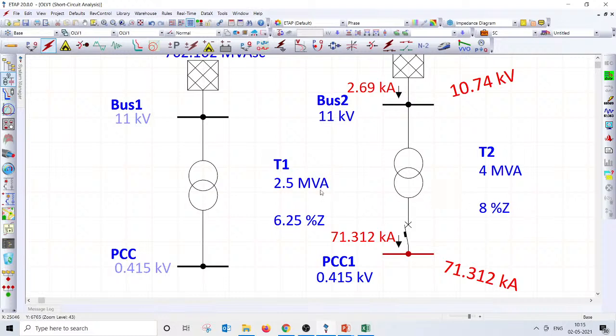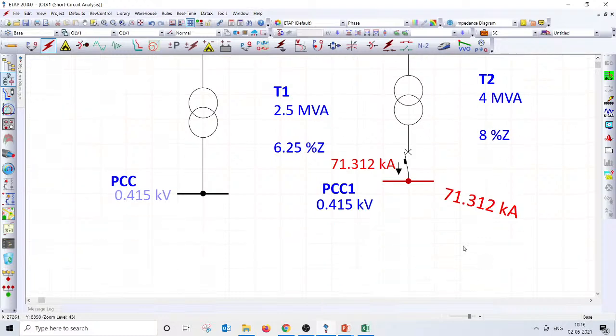8 percent. The fault current is about 71.3 kiloamps, even without any contribution from the downstream. But really it means that downstream you will have quite a lot of motors, so the fault current will be much higher, and even a 100 kiloamp breaker may not be sufficient. And it is not just about the circuit breaker rating, but also about the earthing requirements, right?